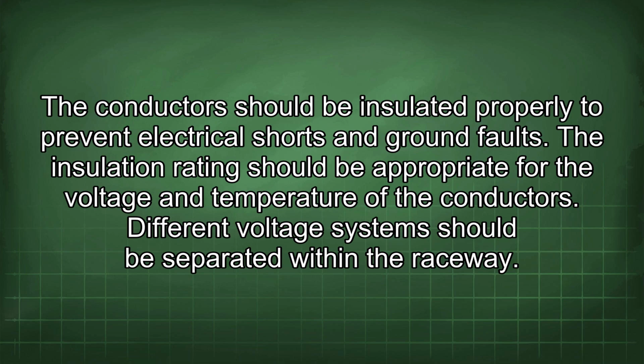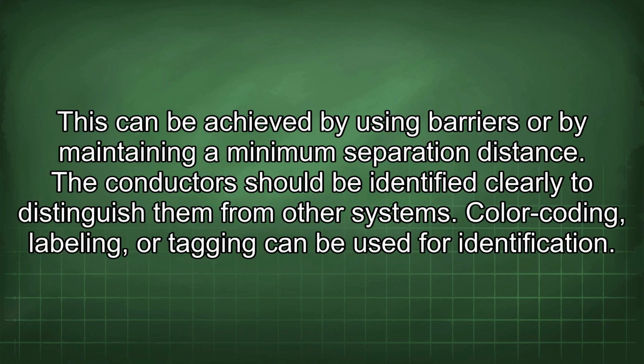The insulation ratings should be appropriate for the voltage and temperature of the conductors. Different voltage systems should be separated within the raceway. This can be achieved by using barriers or by maintaining a minimum separation distance. The conductors should be identified clearly to distinguish them from other systems. Color coding, labeling, or tagging can be used for identification.